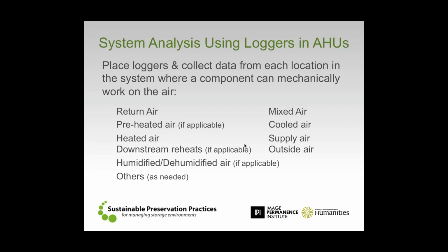And the first step, you know, this is something that we advocate beyond just relying on the building management system, although using the BMS and using those sensor points is certainly a part of this process. But looking for that independent check, that independent information, to make sure that you have multiple points of data and checks and balances across one another, we advocate using data loggers within mechanical systems at each of those locations where a component or the mechanical system can actually do work to the air. And what we're looking for are these comparison points.